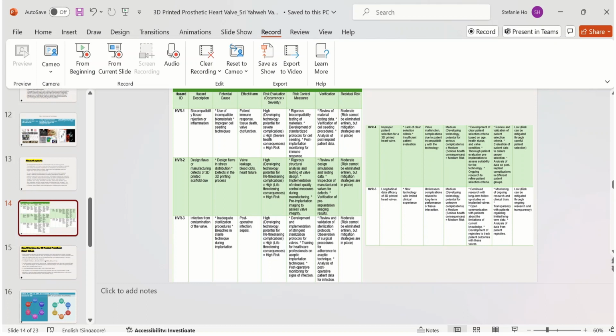Okay, and next we have rigorous biocompatibility testing, material development, and standardized protocols for cell seeding. So this is the risk control: implementation and monitoring for immune response. So how do we verify? Review the material testing data, verification of seeding procedures, and analysis of post-implant patient data. All this will reduce the residual risk, or rather, will still contain risks, and the risk will be moderate. So all this will reduce the risk evaluation, occurrence times severity. Okay, so it's now moderate, cannot be completely eliminated, but mitigation strategies are in place.